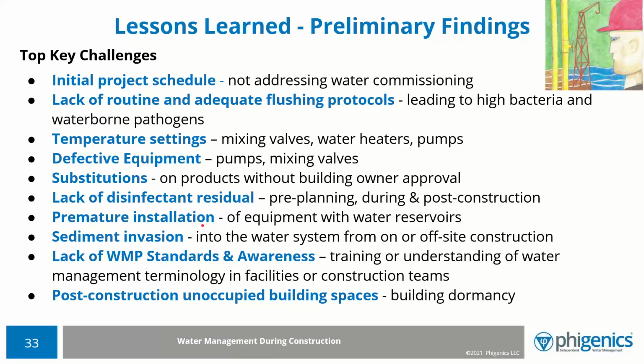Premature installation of equipment that has water reservoirs—the simple example is an ice machine. These things will arrive for nutrition and dietary areas. All this equipment is installed. Nobody uses it. They just do it in the sequence of construction. And then it should be going through preventative maintenance, but who wants to be drinking this water after it's been sitting or making ice and then sat there for months? So all these systems have to be dumped. They have to be cleaned, and your warranty is then going on. You may want to work on the sequence of how these get installed.